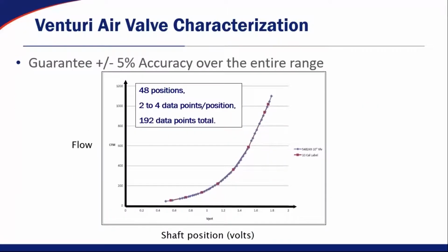The characterization of the Phoenix Controls valves, again, I mentioned it's guaranteed across the entire flow range and pressure range of the valve. And the way that is achieved is when we characterize the valves at the factory, and we do characterize every single valve because every valve body has slight anomalies in it. Every cone package and spring has a very little bit of difference in them. So we value characterizing every single valve. But when we're testing those valves, the valve has 48 positions from min flow to max flow. But when we're testing the valves, we're actually testing more like 192 data points across the entire flow range.